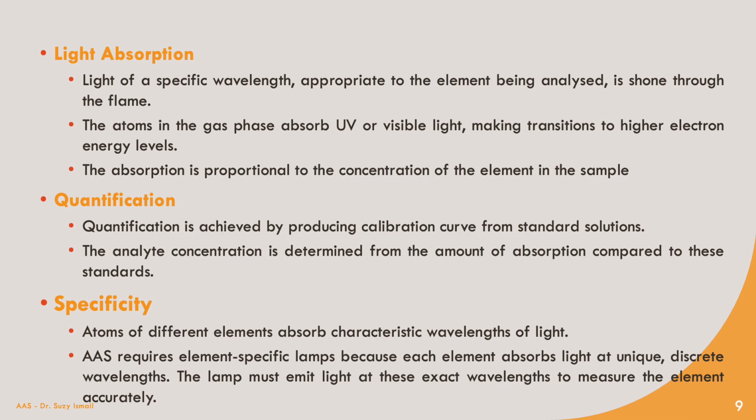And finally, about the specificity. Each element, as I mentioned earlier, has a unique fingerprint when it comes to light absorption. So atoms of different elements, for example copper or aluminium, absorb different wavelengths of light. That's why AAS uses element-specific lamps, meaning that if you are going to check aluminium, you have to use an aluminium-specific lamp.